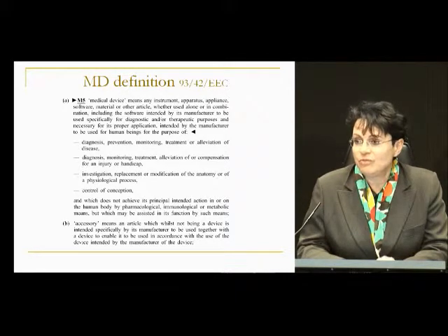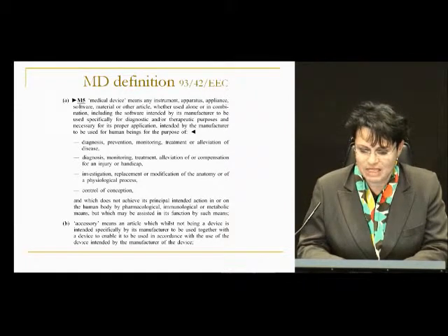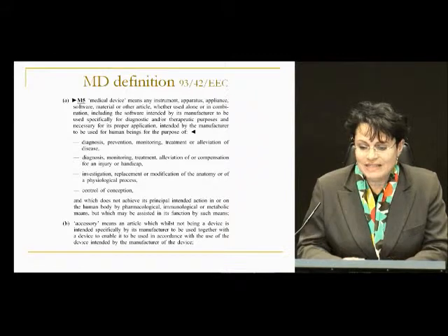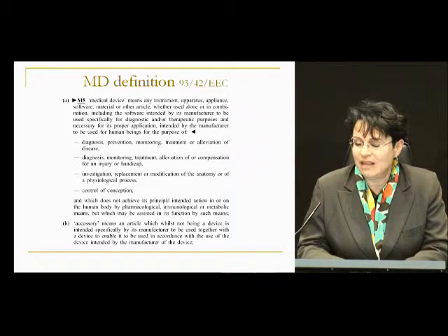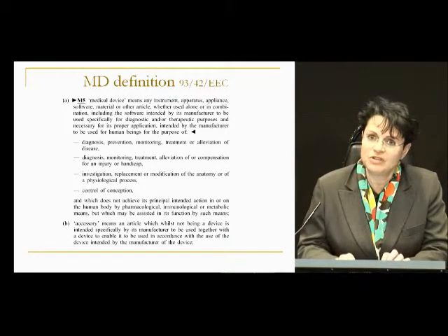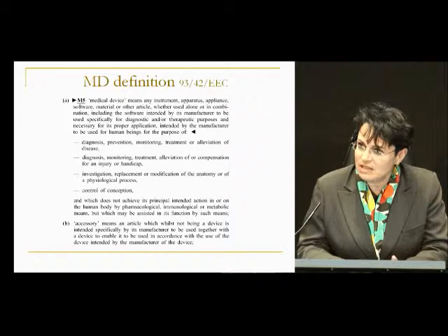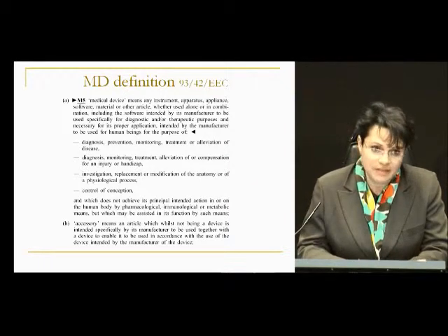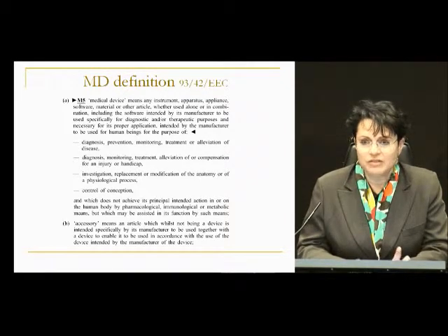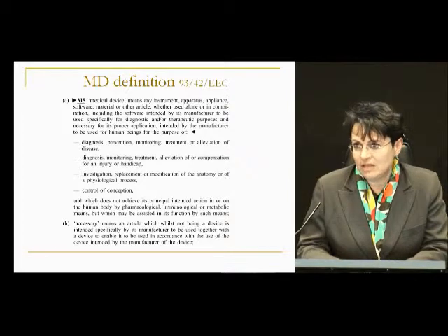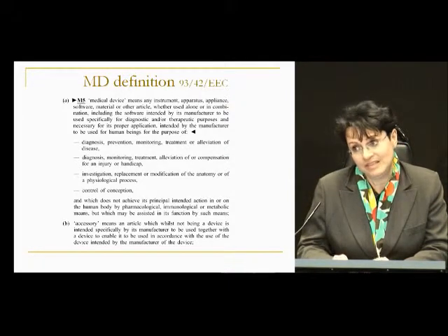It means that a huge training must be done, a huge communication as well, every time a device is placed on the market. So, intended by the manufacturer, says that the manufacturer is responsible for placing the device on the market and is responsible in front of the competent authority, the Ministry of Health, in France AFSSAPS for the time being, or the notified body, which is the organism in charge of authorizing the CE marking.